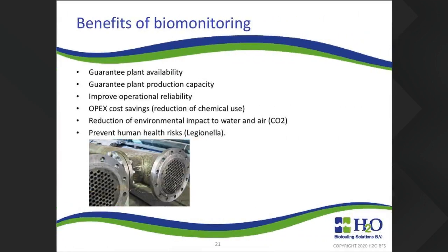Now, the benefits of biomonitoring, this is the last slide of my presentation. It provides a guarantee on plant availability. So there is no unexpected outage, there is no risk for head loss, which results in an outage. Production capacity guarantee. So you can be guaranteed that your desalination plant will produce water according to your contract. You can be guaranteed you can produce power according to the specification of the power plant. So there is no risk for biofouling in that area.